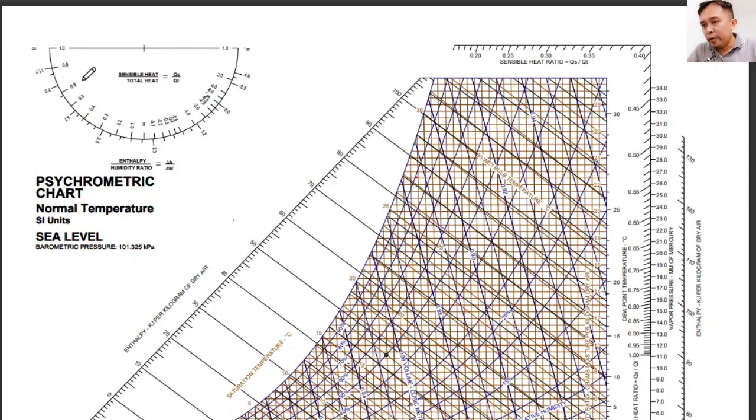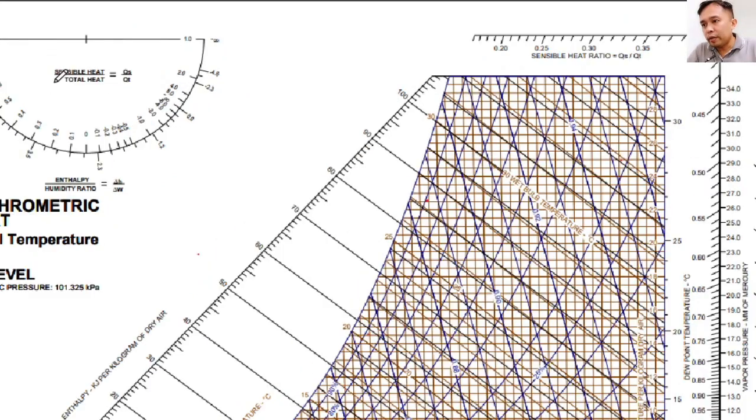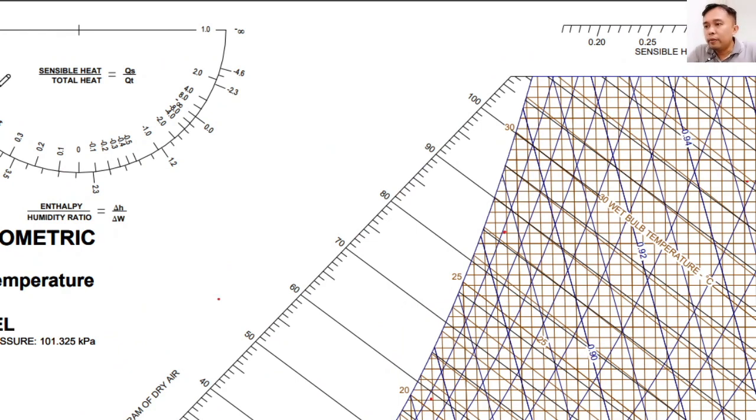In the upper left corner, we have your protractor, where you can find the sensible heat over the total heat ratio. So we have the sensible heat ratio, and the values are read from the inside. And finally, you have your enthalpy humidity ratio where the values are read from the outside of the protractor.